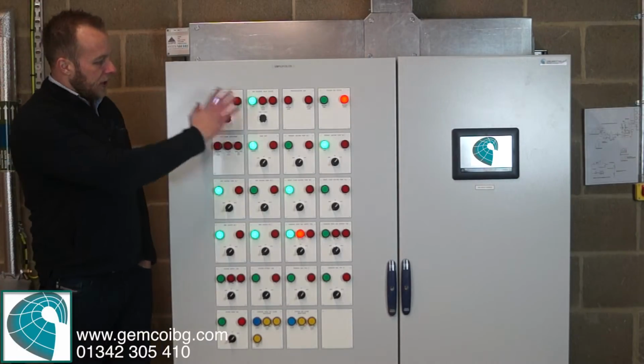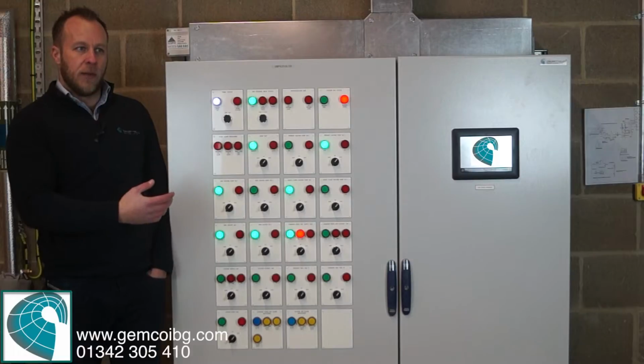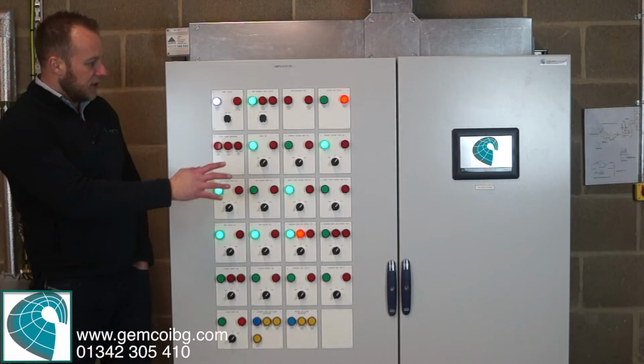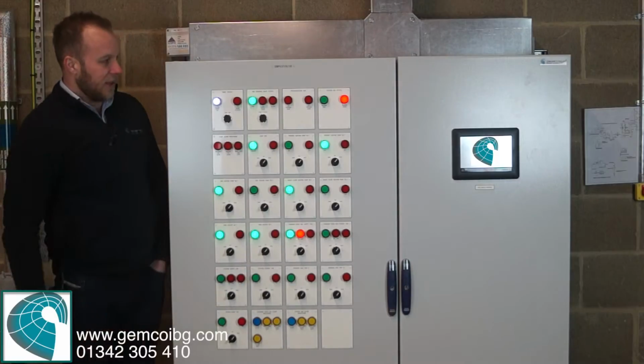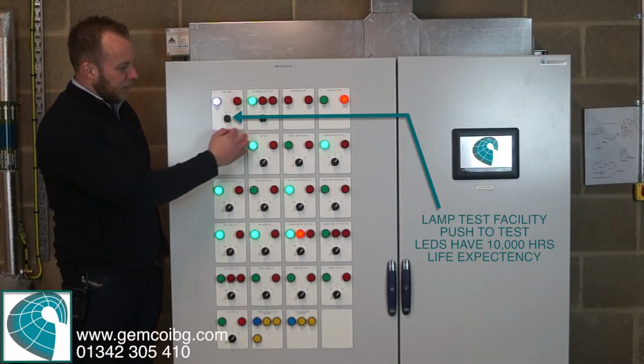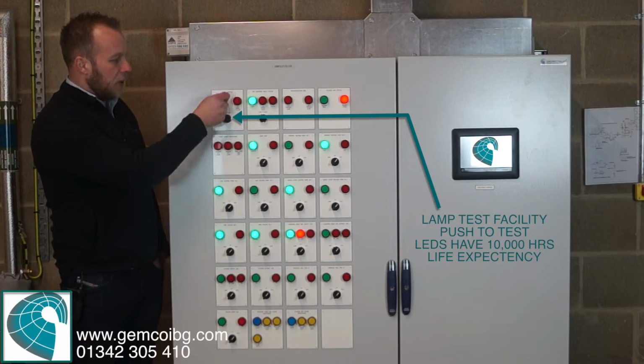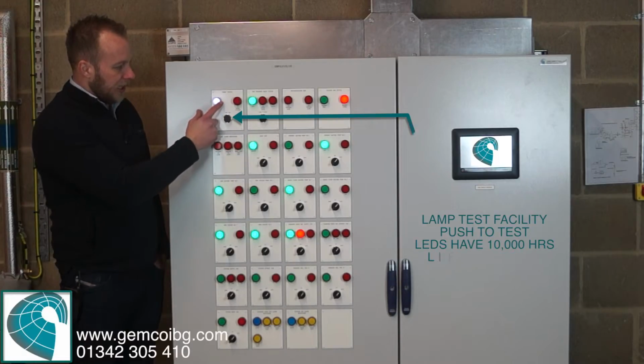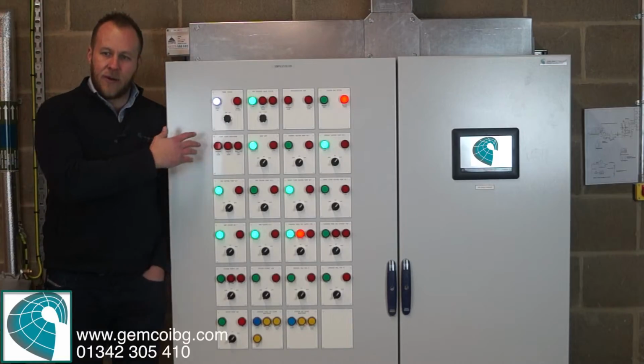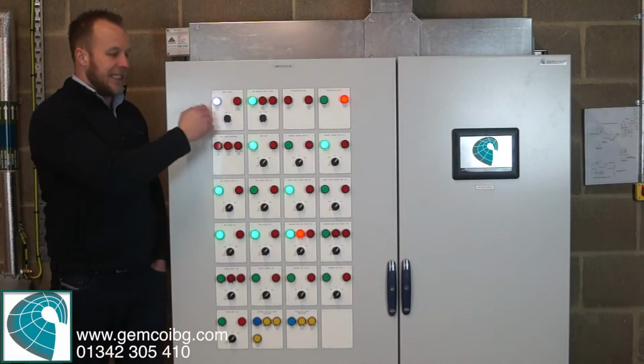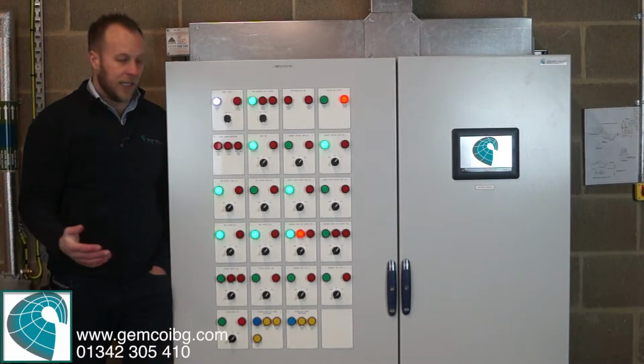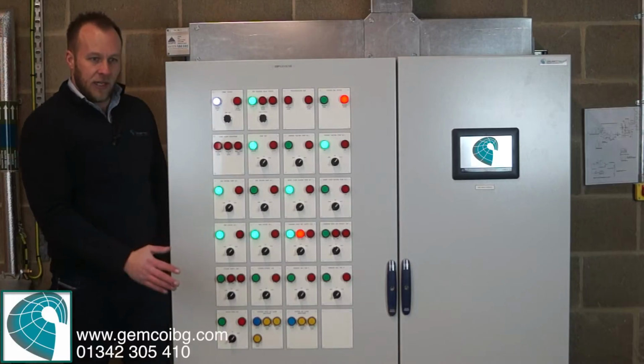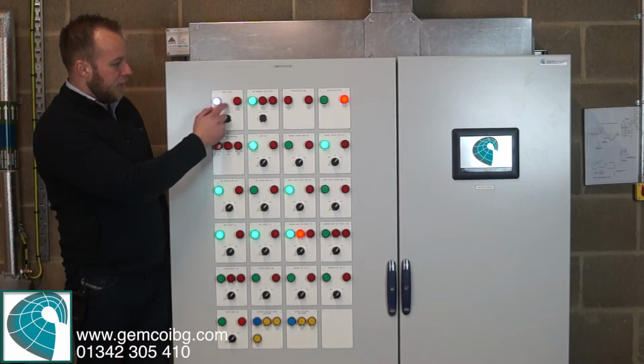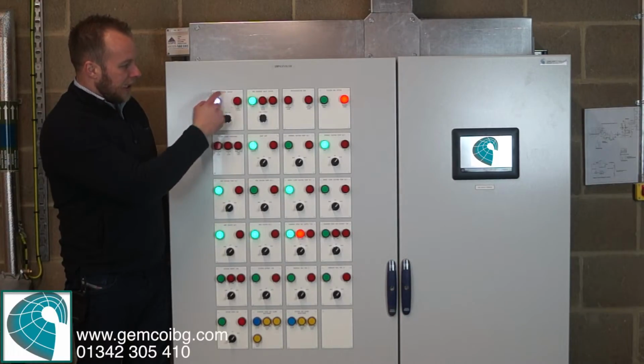Now, I'll run you over the panel first, and then I'll talk a bit more about the intelligent side of the control. So, first of all, these lamps and switches are very conventional, and the first label we come to is the panel status. This is probably the most important one, because this control circuit live lamp will let you know if your control circuit's live. Okay, so if that's out, you're not going to have any plant running. Okay, if that's lit and your plant ain't running, then you can work through the process. But that's one of the most important lamps, and this is the panel status label, which really shows you the two most important things.